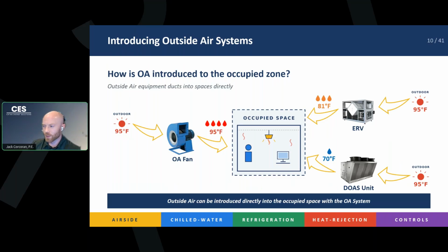So this is just another way of taking a look at it. We can bring the outside air directly into the space. This way, as we said, the outside air dumps the hot and humid 95-degree air on the left side directly into our occupied space. You're going to have a hot and humid space. That's just the way it is with an outside air fan, but it's easy and simple. There's nothing cooling or heating the air. An ERV, on the top right, brings that outside air at 95 slightly down. In this case, to an 81-degree temperature with slightly less moisture in it, only 3 droplets instead of the 4 we had with the outside air fan.